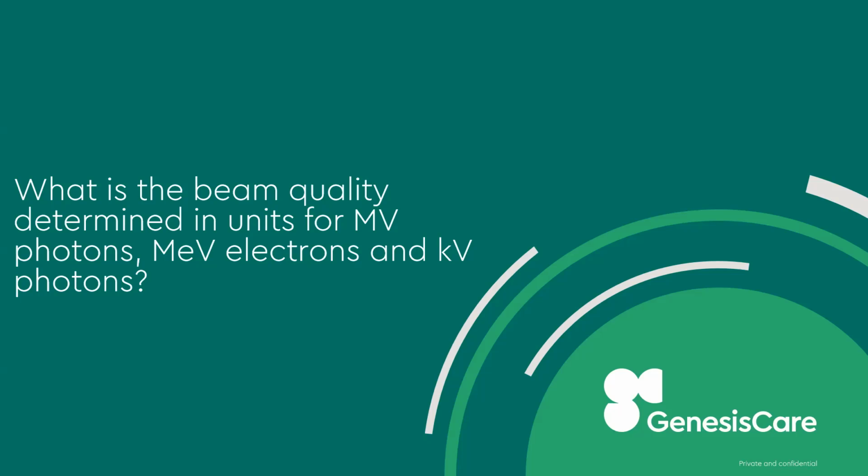So for photon, we are defining at a certain depth, 10 cm depth. We have a specified number that we are expecting. And for the electron, what's that number? What are you doing there? 66.7 something. No, there's the number, but what are you looking for? Percentage depth dose. Yeah. If you are using TG-51, then that's the protocol. But if you are using the IAEA, then what's the beam quality? Then TPR 20/10. So yeah. What about the electrons? Electrons is R50. We measure the R50 for that beam quality.